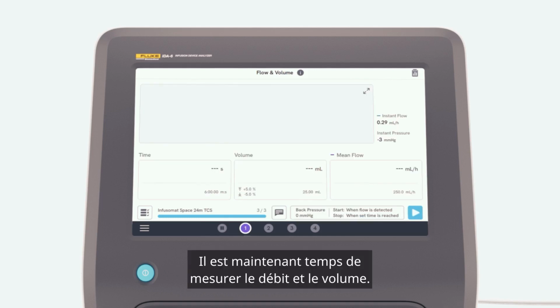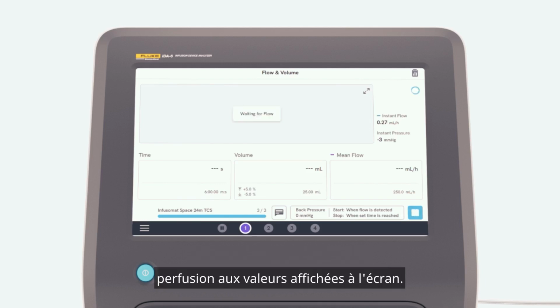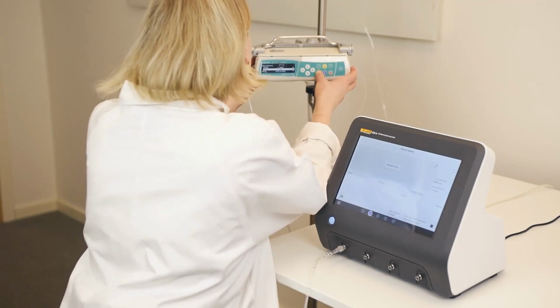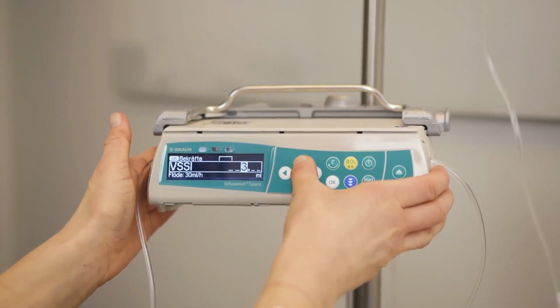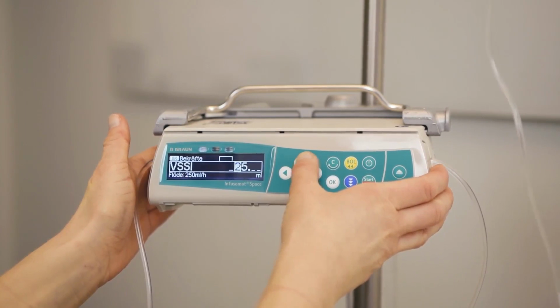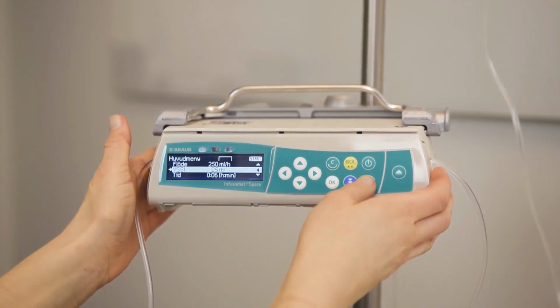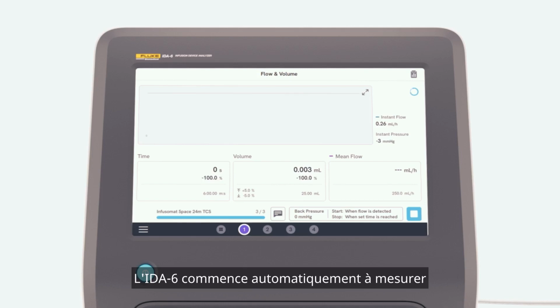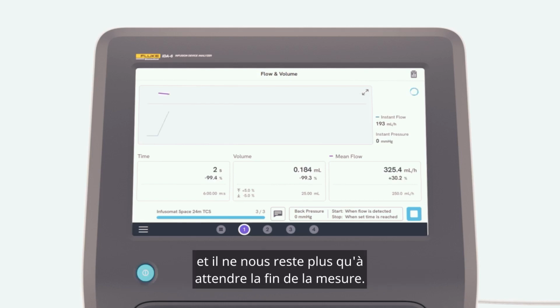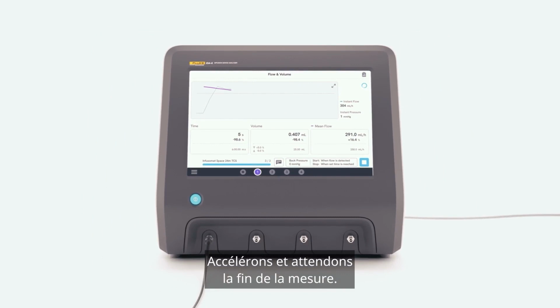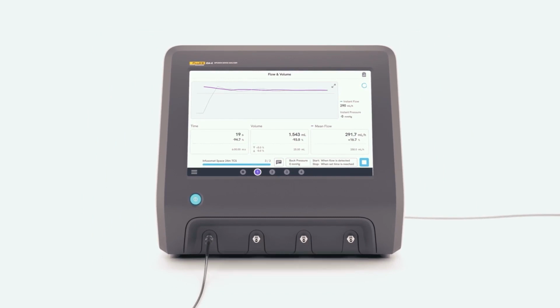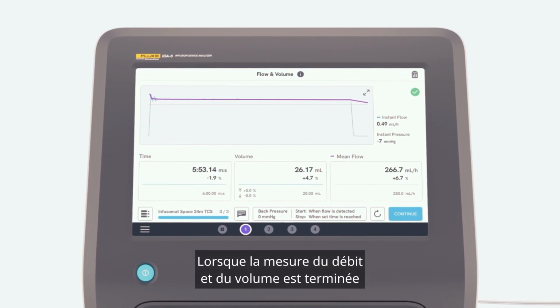Now it's time for a flow and volume measurement. Let's press the Run button and then set the infusion pump to the set values that are shown on the screen. The IDA-6 automatically starts measuring, and all we have to do is wait for it to complete. Let's speed it up and wait for it to finish. When the flow and volume measurement is complete, we can see the final values and the result.